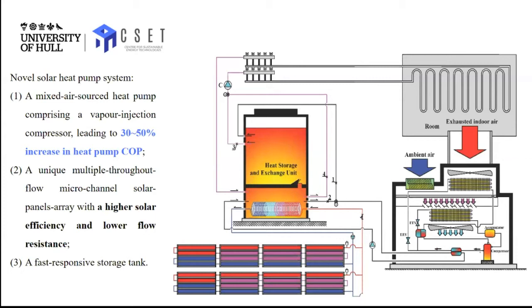Second technology is a double source heat pump with a vapor injection compressor. With this kind of heat pump, we try to recover heat from both ventilation air, exhaust air, as well as ambient air. We have two evaporators connected in series. We got exhaust air pass across the first evaporator, then we got exhaust air and ambient air mixed up and into the second evaporator.